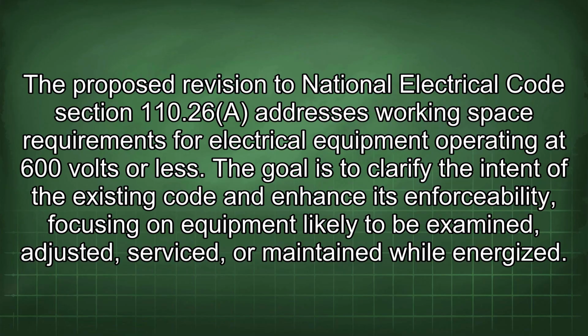The proposed revision to National Electrical Code Section 110.26 addresses working space requirements for electrical equipment operating at 600 volts or less. The goal is to clarify the intent of the existing code and enhance its enforceability, focusing on equipment likely to be examined, adjusted, serviced, or maintained while energized.